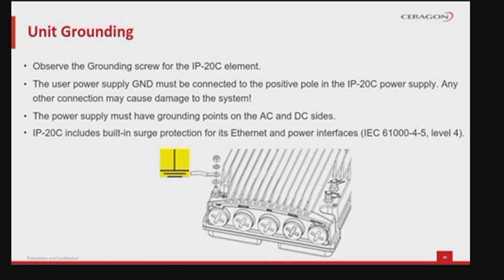The user power supply ground must be connected to the positive pole in the IP20C power supply. Any other connection may cause damage to the system. A 2-pole circuit breaker, a branch circuit protector, suitably certified in accordance with applicable national code and regulations, rated maximum 20 amperes, shall be installed for full power disconnection in a building installation.